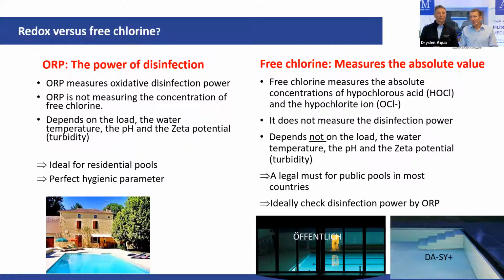So therefore, as we know, it's a legal must in public pools. I think in all countries that I know, free chlorine measurement and minimum free chlorine levels are a must. But ideally, it should be combined with an ORP controller as well. This is how we do it in Germany, Switzerland.